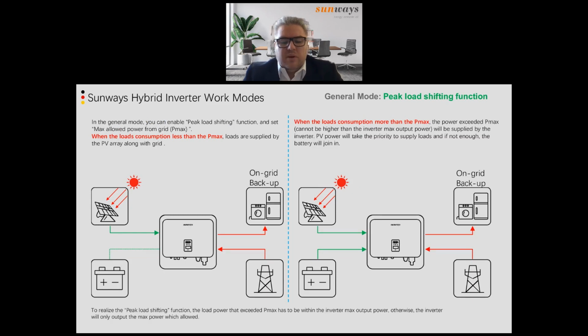A variation of this is that you can save the battery for a time you may need it, especially in countries with grid instabilities. When you want to save the battery, you can set this peak load shifting function, and limit the power from or to the grid to save the battery. So if there's no need to use the battery, you can take power from the grid to keep the battery full for when you may need it because of grid problems.